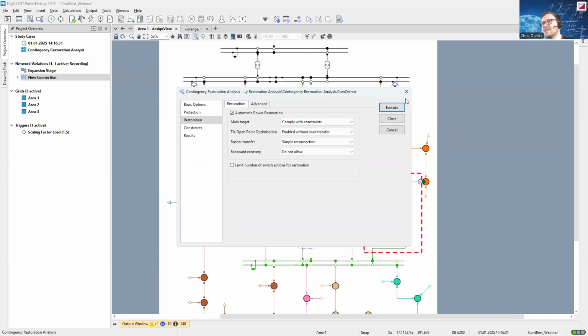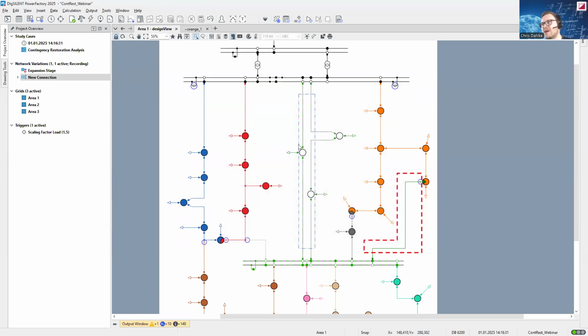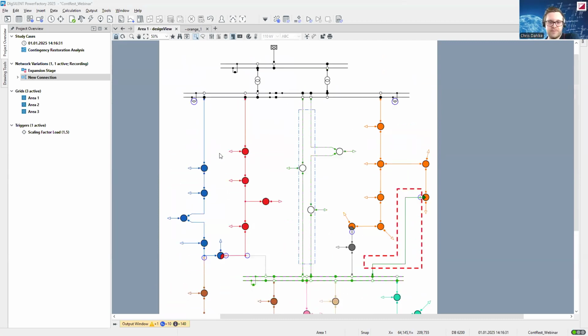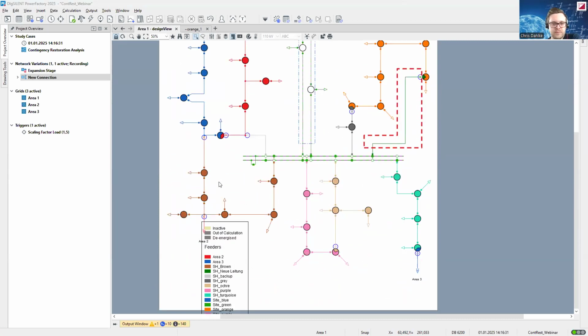Next question: you mentioned that feeders are required for the tool. In the tool, is it specified that they are required? Are there any requirements for the feeder? Do they need to be radial? Yeah, so the tool will give you a hint when there are no feeders, that it cannot do this. There's a warning message. In some cases, it will automatically create temporary feeders. When there are very easy arrangements where feeders are missing, it will auto-create feeders.